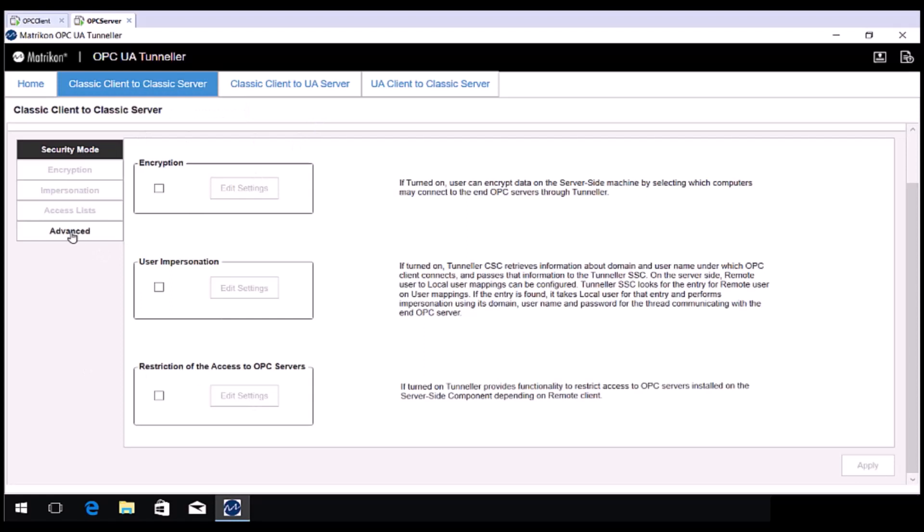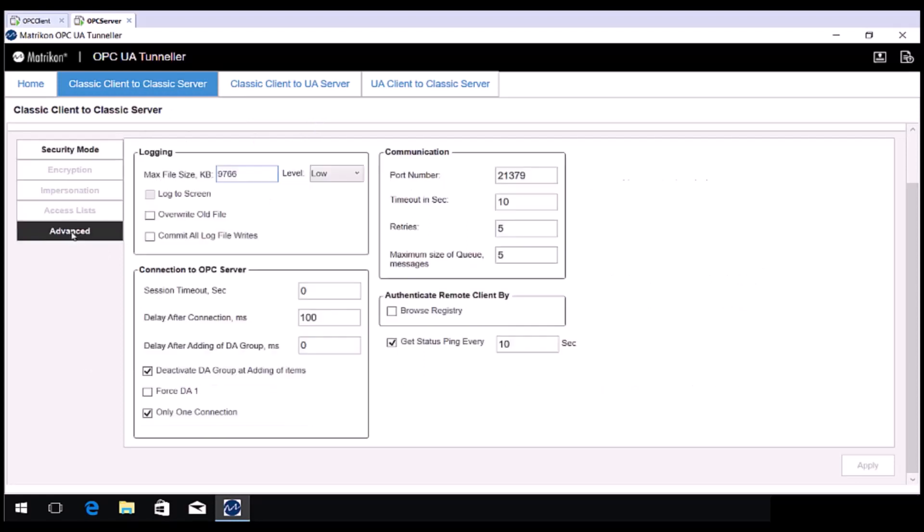Moving on to the Advanced tab, these settings generally will not need adjusting. If you want to use a different TCP port, you can adjust it here. If you are using an OPC Server that supports an older specification, such as OPC DA 1.0, you may need to enable the Browse Registry option here.